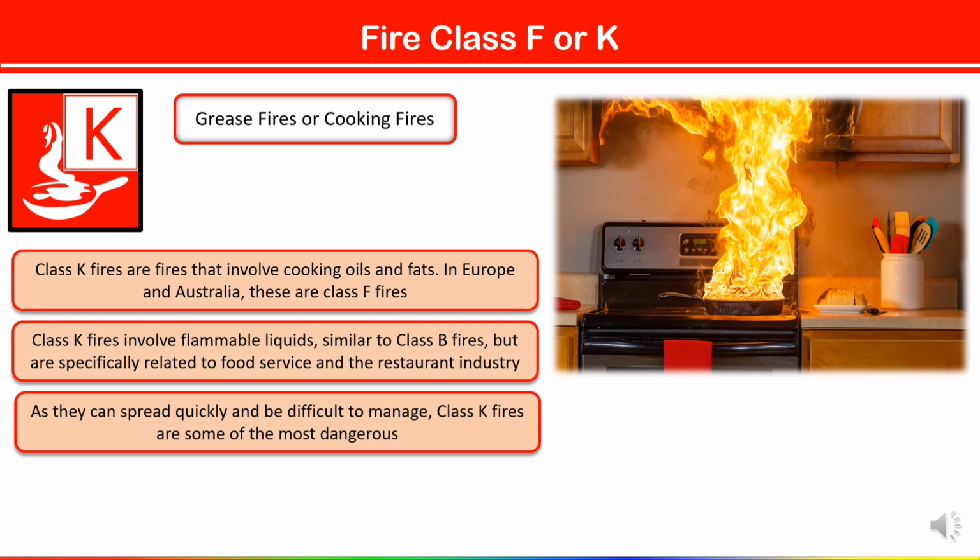Never use water here in case of a class K fire, because adding water to a grease fire causes violent splattering, which can spread the fire and cause severe burns. And after that you have to turn off the heat source. If safe to do so, turn off the heat to stop further heating of the oil, which can reduce the risk of reignition. And then use specialized extinguishing agents.